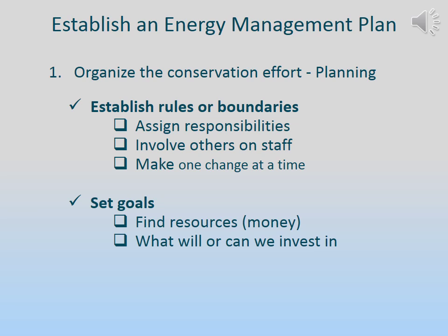The other thing to consider are the costs associated with having that measure implemented. Do we have to pay an electrician or a mechanic? Do we have to modify something? What is the cost of labor to implement this conservation measure? We need to keep in mind that a lot of these considerations, suggested at times, do not include labor costs. So if we use our staff, then that labor is cheap. But if we do not have these labor experts on staff, and we have to bring somebody in, then all of a sudden we may have doubled the cost and payback period.